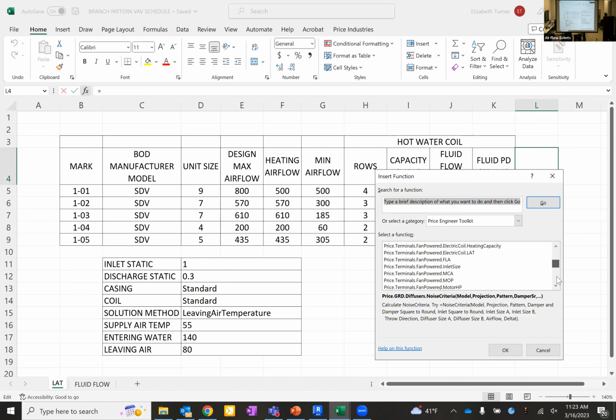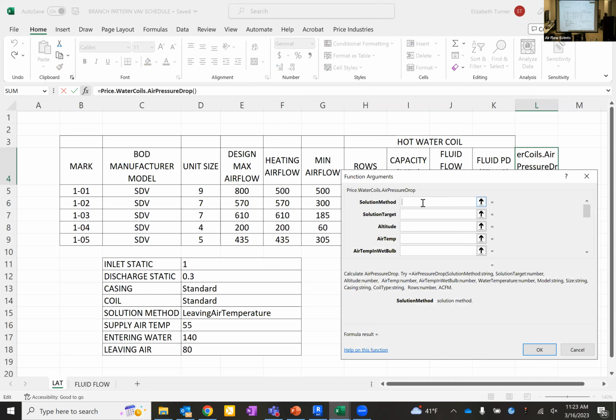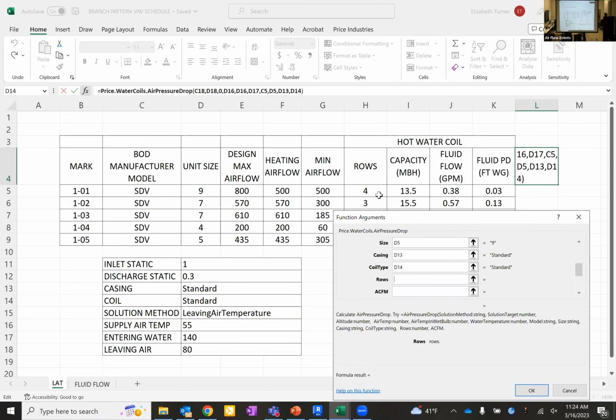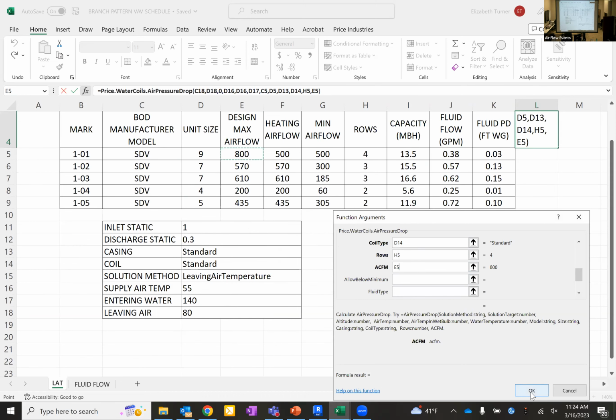So I'm going to add my function here, go water coil, that's water pressure drop, water coil air pressure drop. My solution method is leaving air temperature, solution target 80 degrees, altitude 0, entering air temp 55, wet bulb, match 55. Water temperature. Model is SDV, size, casing standard. Coil type is standard, my rows are referenced up here. Airflow is heating airflow. Actually, we want max pressure drop, so I'm gonna do design airflow. There you go. And I'm gonna click OK.